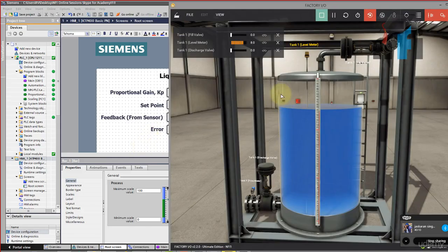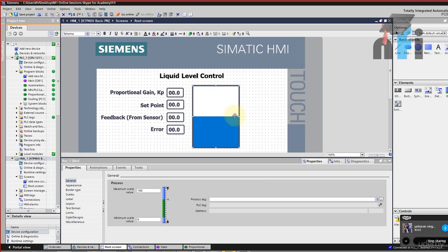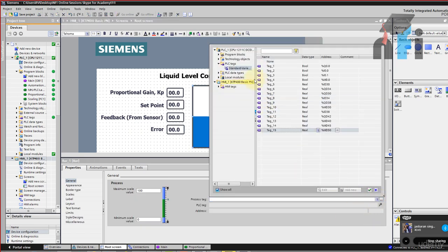One more thing I want to say: we are referring to the software in which our input is ID 30. It's not always ID 30. If you're using analog input, the addressing will be different, so you have to make sure what address you are using for analog input. Similarly, for analog output, it's QD30 here, but in real hardware it's not QD30. It's different, which is written in the manual. So you have to use the addresses which you are actually using in the plant. The rest of the process is the same. So this is the tag, and the tag should be ID30.